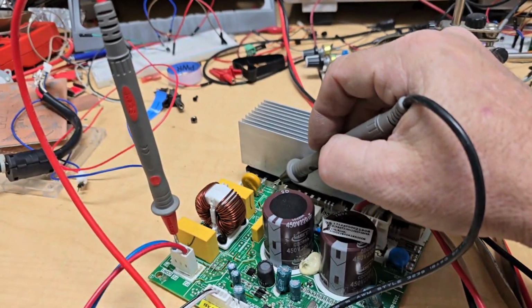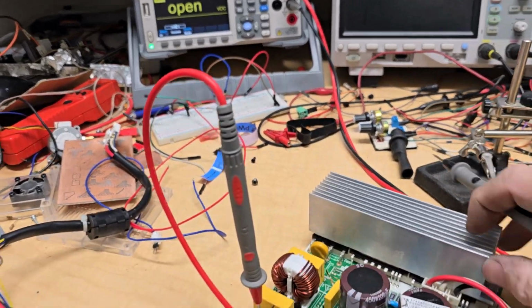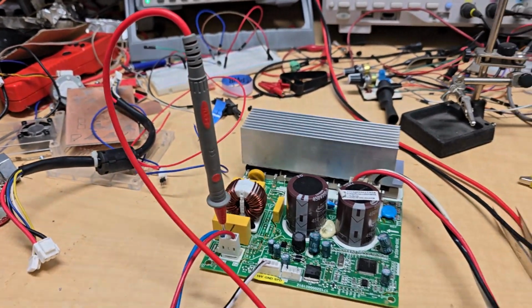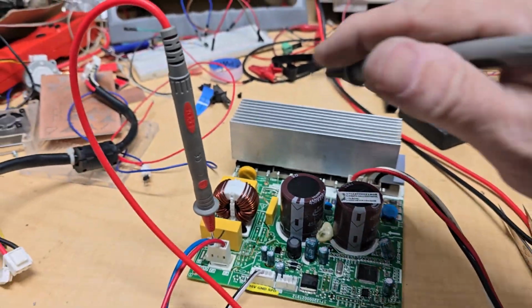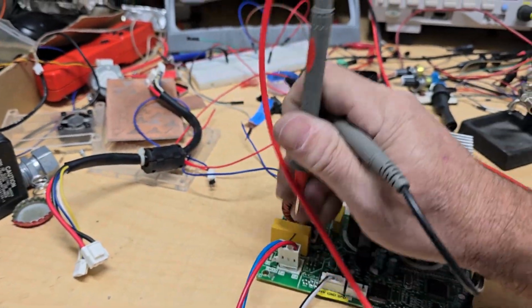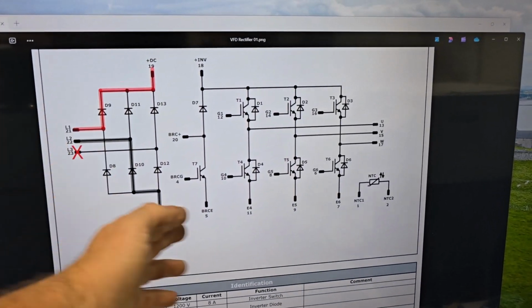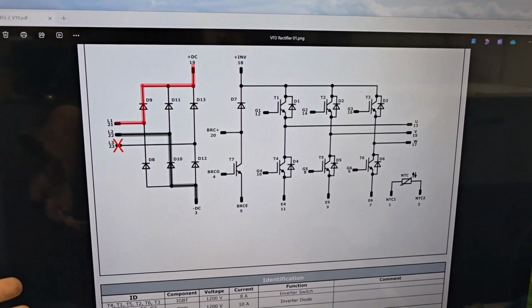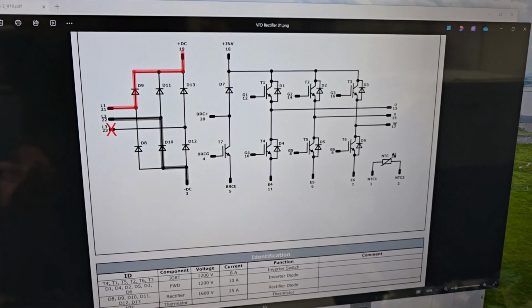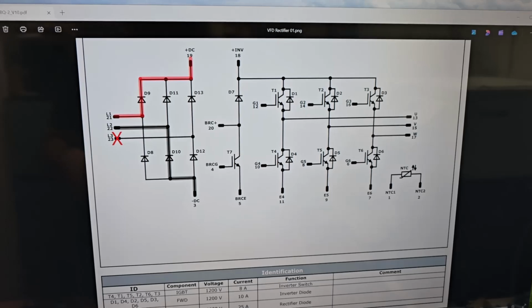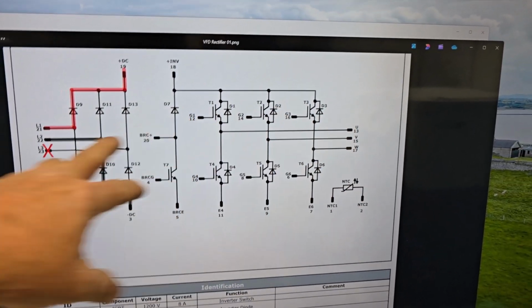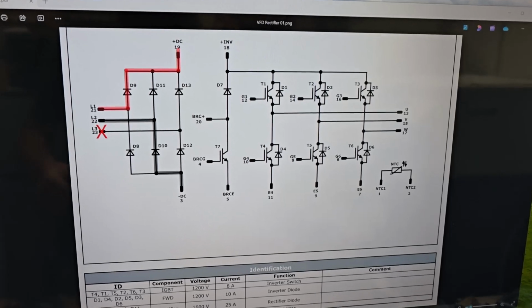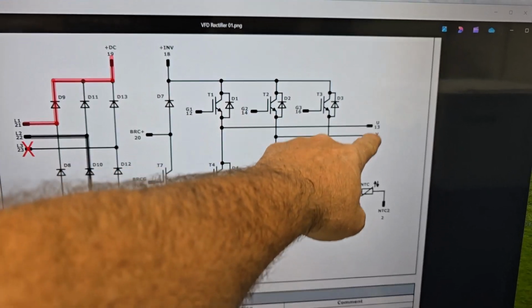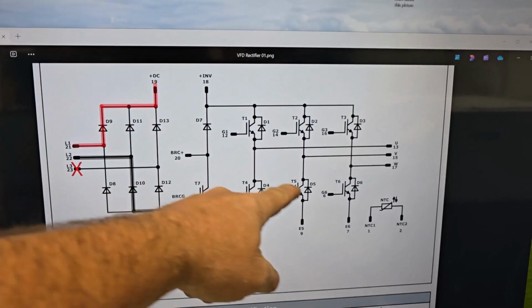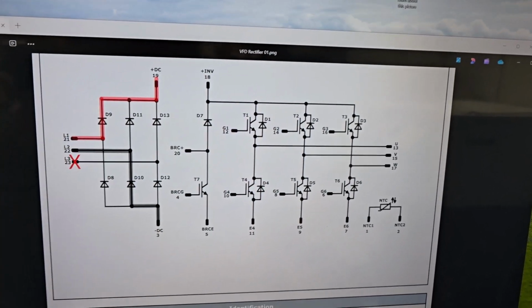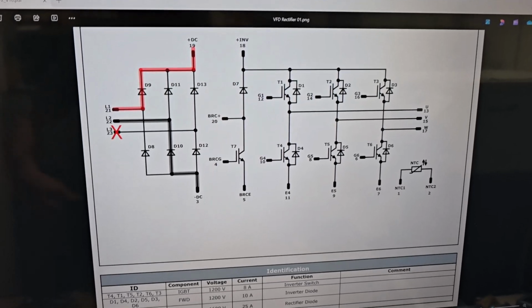This is how you want to check out your rectifiers on your IPMs anyway. A lot of people don't really check these anymore, but you could check outputs likewise also since I'm in here. So here's a layout for a VFD or IPM module - this module has the rectifier built in, same general layout of all the MOSFETs or IGBTs on these type of units. You could check your outputs, your U, V, and W going out to the motor, to the DC bus, to see if any of the drivers are obviously shorted or blown.